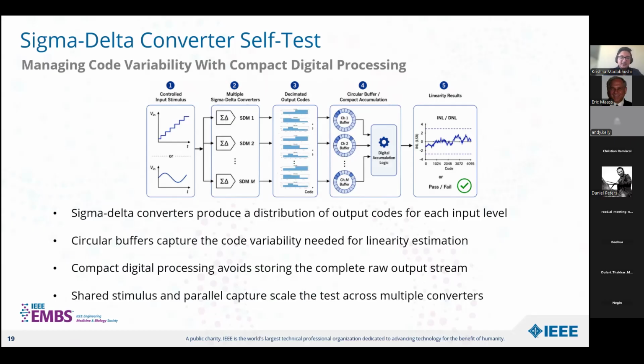The digital processing afterward converts the accumulated data into useful information, such as the linearity, INL and DNL, and it can also be a compact pass-fail if we already established a baseline. During the production test, a more complete version can establish that beginning-of-life linearity, like we talked about. And during operation, a reduced test can revisit some selected input levels, look at the signature, and compare it to the baseline. We have now followed the signal through the power, timing, and also the conversion. The final thing I'm going to cover in this presentation looks outward at the leads, electrodes, and the tissue path itself.